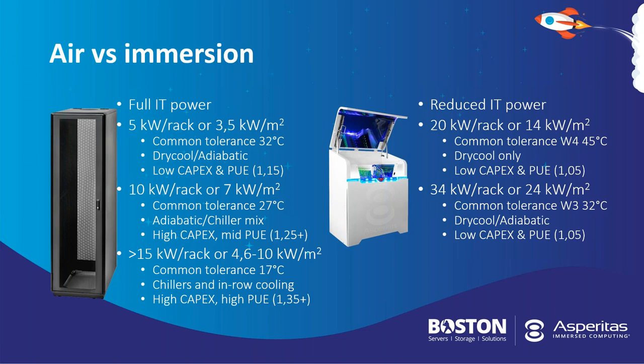Now, this is where immersion starts playing a whole different ball game. The standard deployments that we're doing right now are in line with one of the platform solutions that we jointly positioned at CloudFest recently. If we're looking at 20 kilowatts a rack, that translates to approximately 14 kilowatts per square meter.